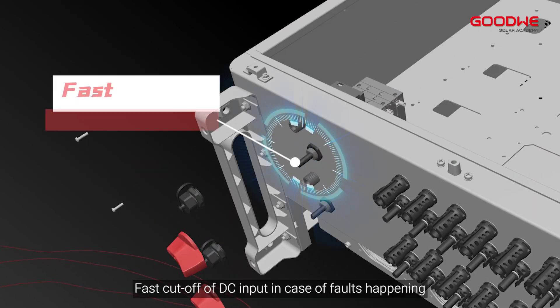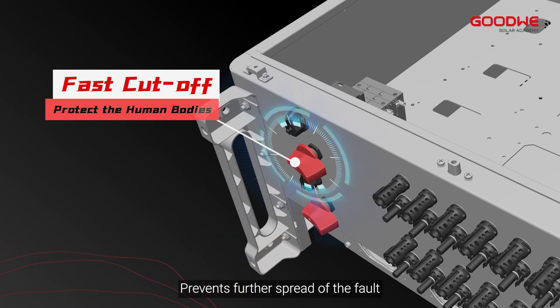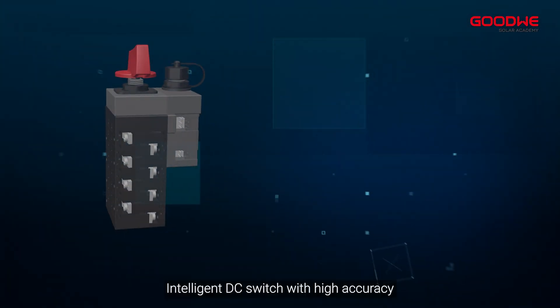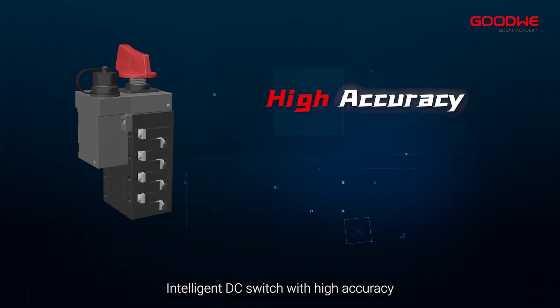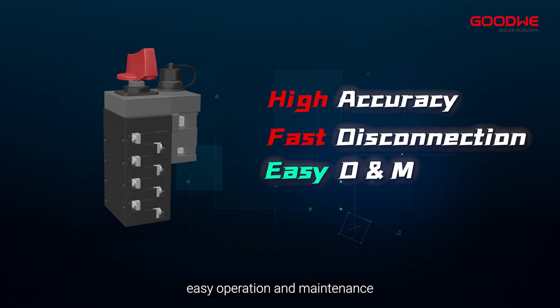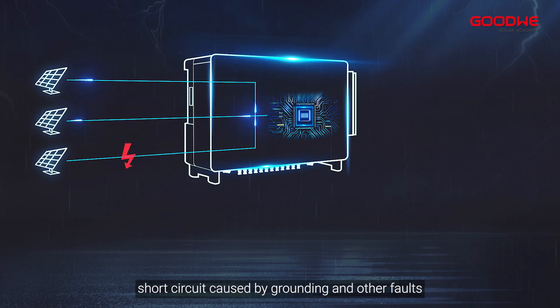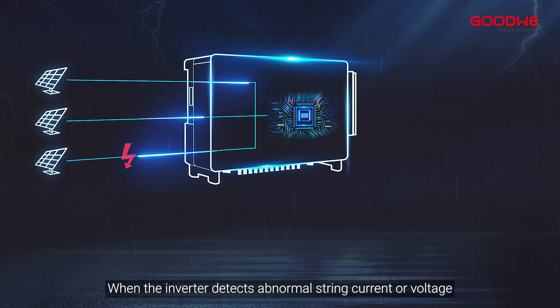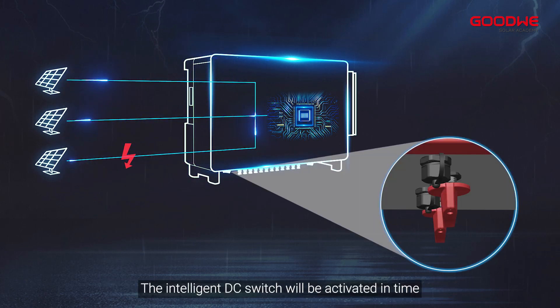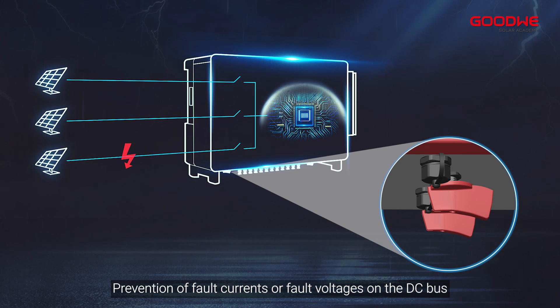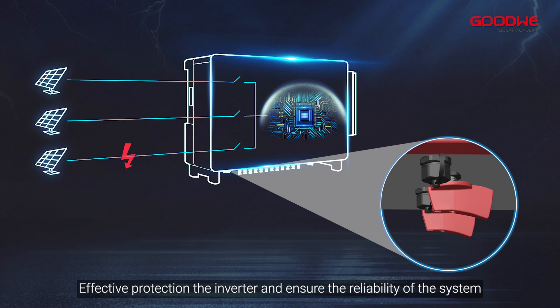The intelligent DC switch enables fast cut-off of DC input in case of faults, preventing further spread of the fault and resulting inverter failure or even personal injury. With high accuracy and fast disconnection, when the DC side experiences current backflow, short circuit caused by grounding, or other faults, the inverter detects abnormal string current or voltage and the intelligent DC switch is activated in time for precise cut-off of the DC side.